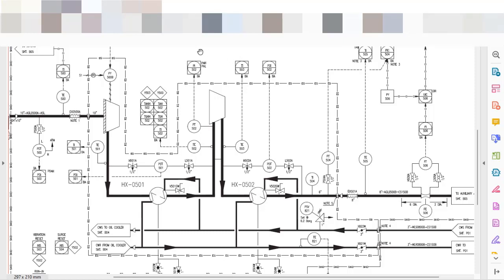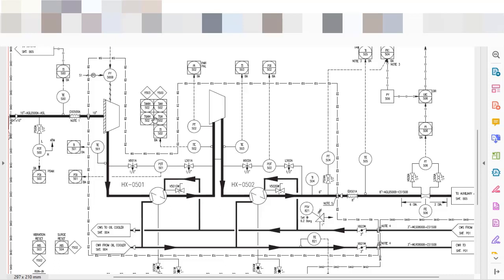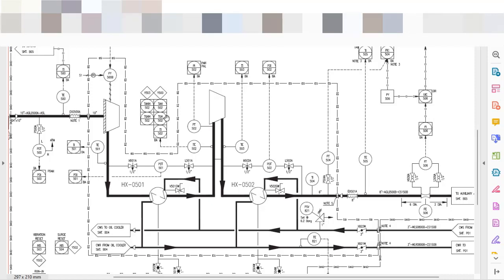In my control system, I will have also, in some cases, besides the information of temperature here, I will have an alarm for high temperature and I will have a signal or a set point for shutdown temperature. So the TSHH is a switch for shutdown of the compressor and I will associate that with an alarm. The same for the alarm for high temperature. So I have a switch for high temperature that will lead to the alarm of high temperature.